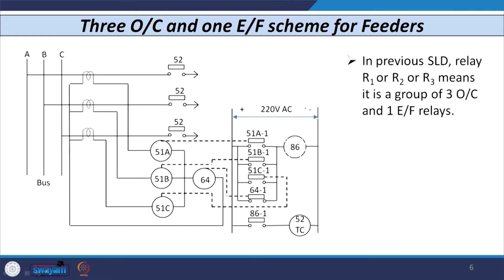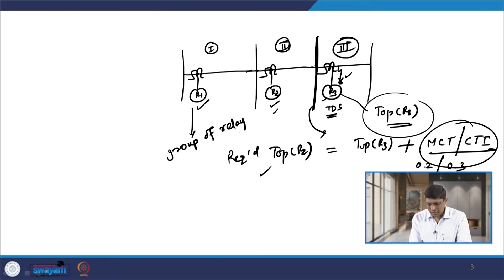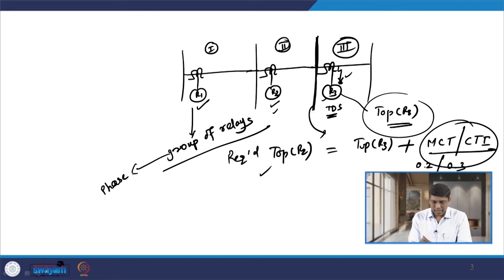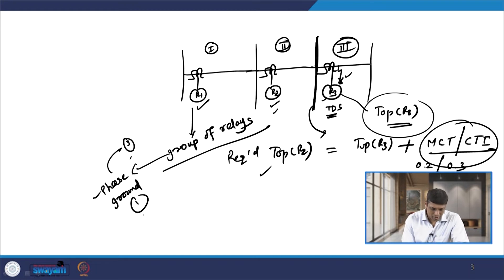With this background, let us consider the three overcurrent and one earth fault scheme used for feeders. Relay R1 is nothing but a group of relays: it has phase overcurrent relays and a ground overcurrent relay. We normally have three units of phase relays and one unit of ground relay. When you have three units of phase relay and one unit of ground relay, it is known as the three overcurrent, one earth fault scheme.